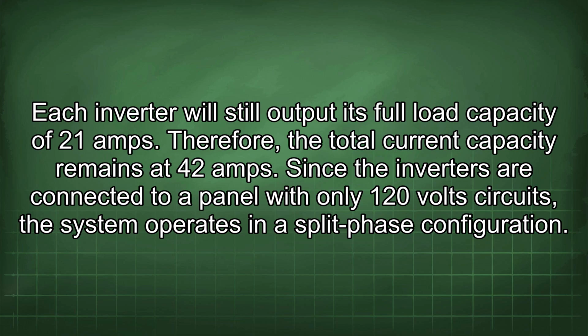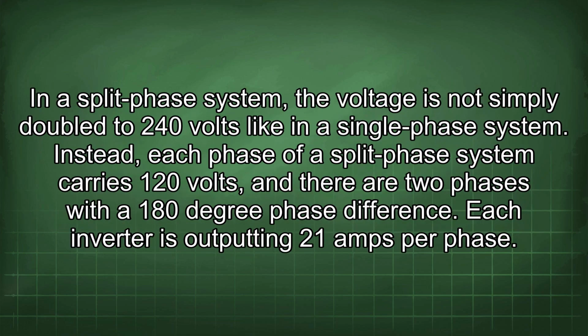Since the inverters are connected to a panel with only 120-volt circuits, the system operates in a split-phase configuration. In a split-phase system, the voltage is not simply doubled to 240 volts like in a single-phase system. Instead, each phase of a split-phase system carries 120 volts, and there are two phases with a 180-degree phase difference.